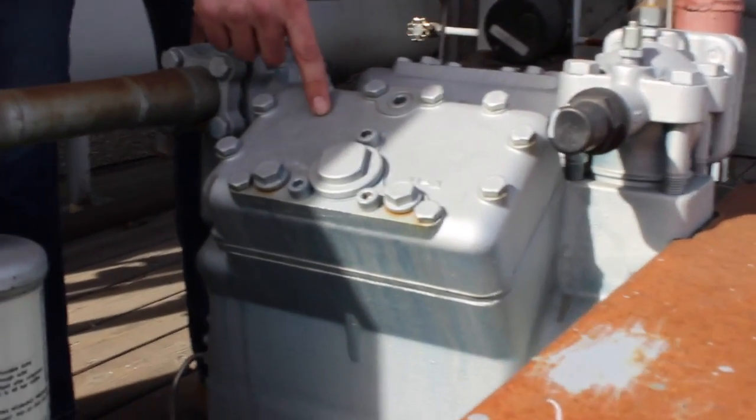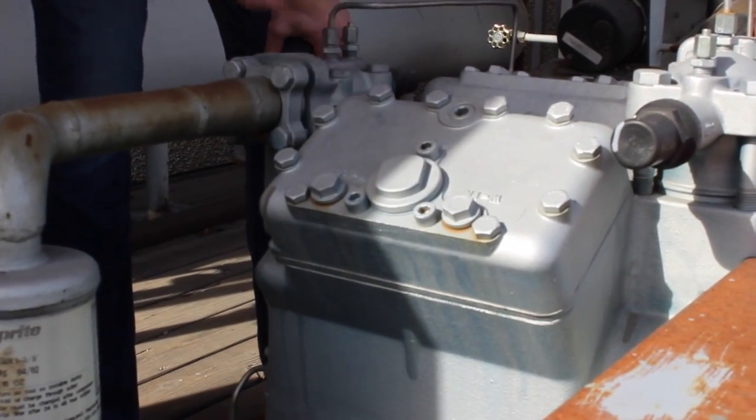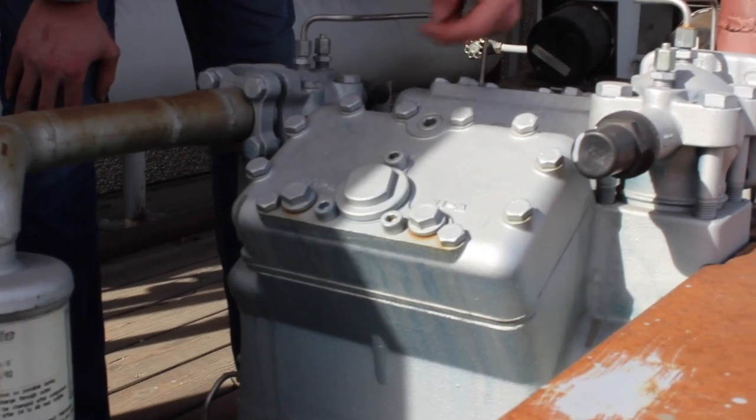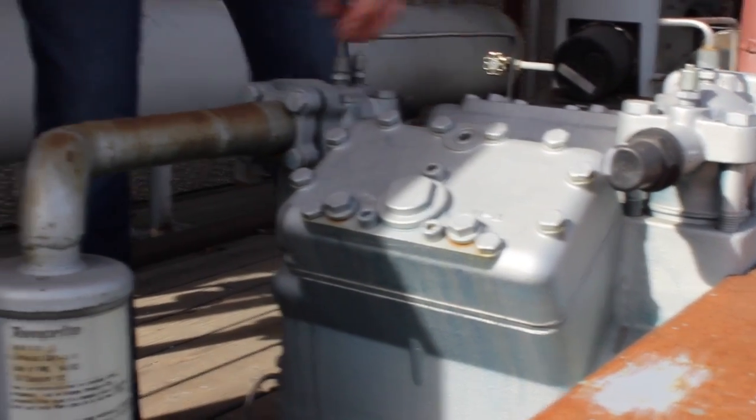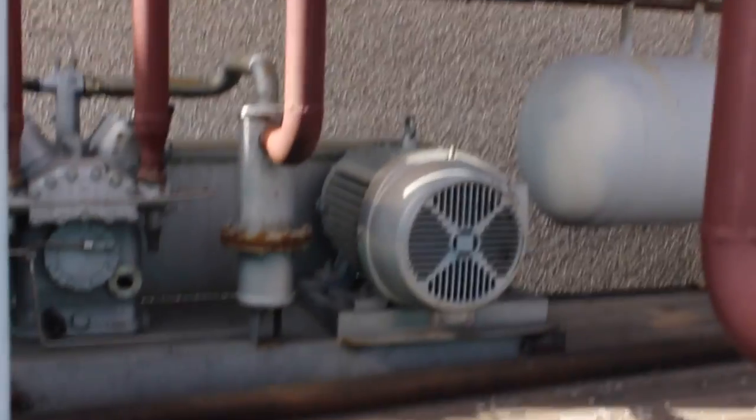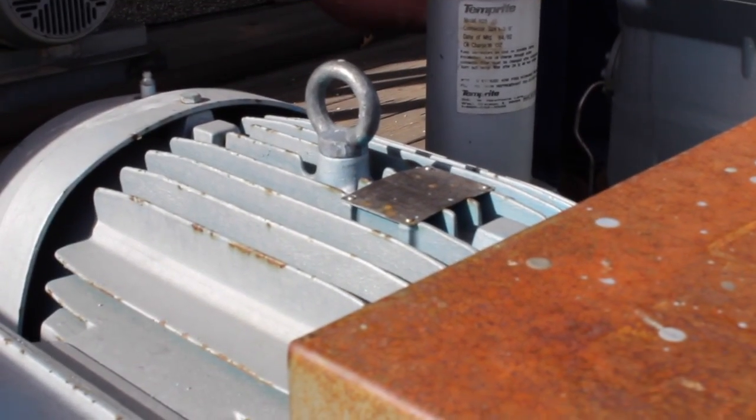This is the first stage compressor. It takes the vapor and increases it to a higher pressure before it travels to the second stage compressor, which allows it to create a lower temperature. The first stage compressor is powered by a belt-driven, three-phase, 15 horsepower motor.